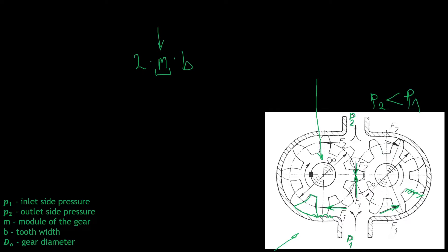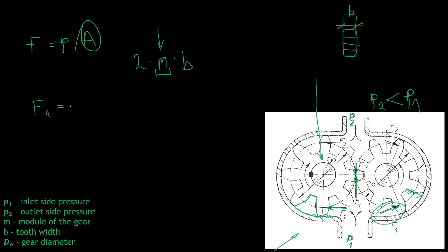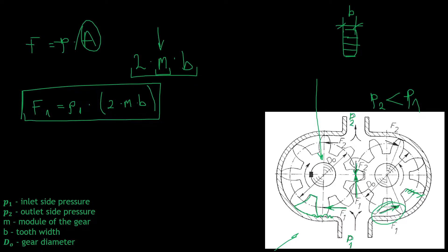If you look at this gear from the side you will see something like this — this is from the side and this is actually B, the width. So if you want to calculate the force that pushes this gear, force F1 is equal to pressure times the area upon which the pressure acts. So we have P1 times the projection on the radial plane, which is 2 times M times B. This is how we calculate the force that is pushing the gears.